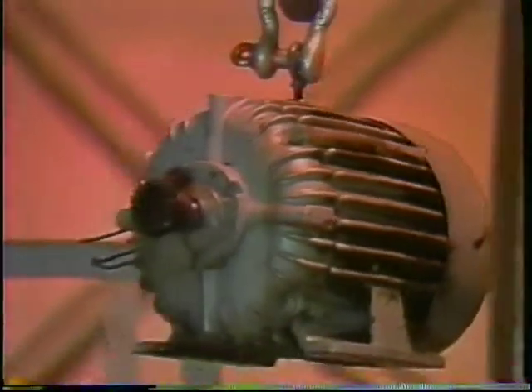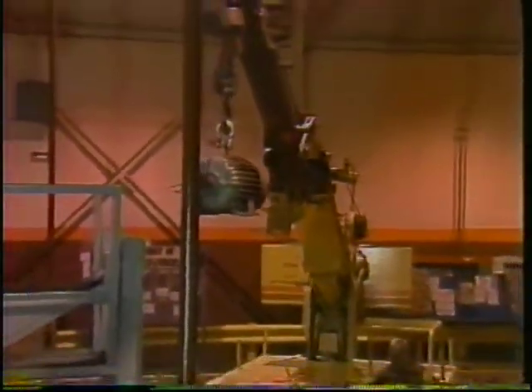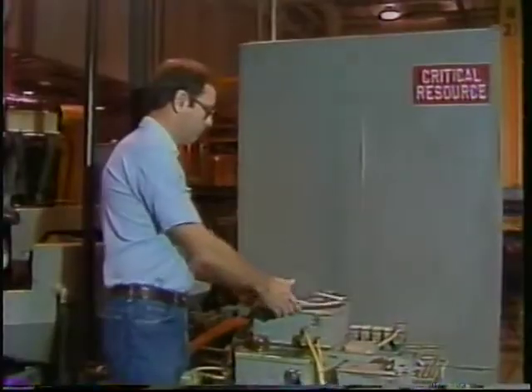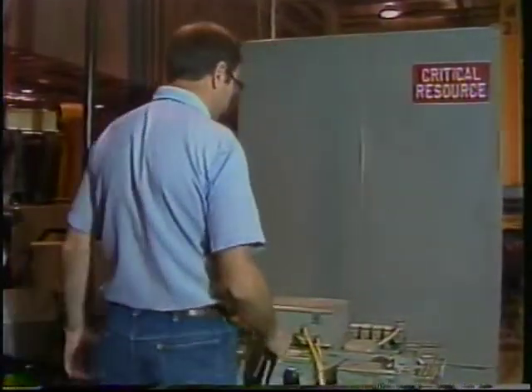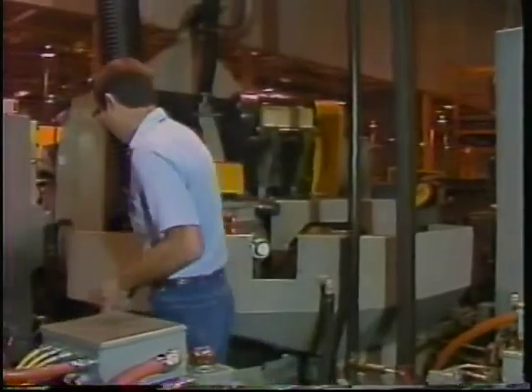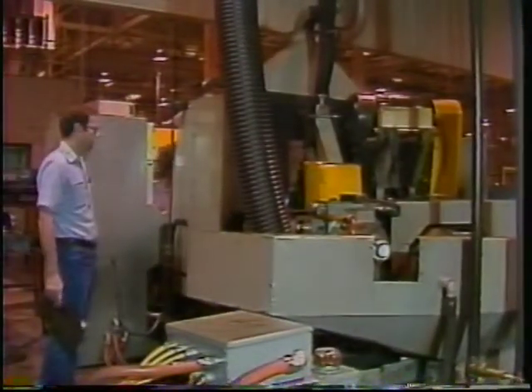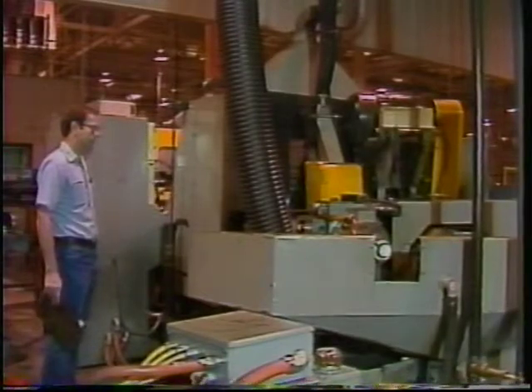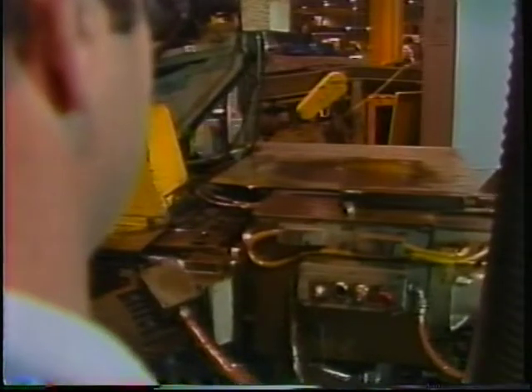Was the old motor especially dirty, or was it working in an especially hot environment? Talk to the operator or pull the work records on the motor to see if it has a history of tripping its overloads or breaking down some other way. You might also make sure the operator understands the limitations of the motor and has not been overloading it in some way or starting and reversing it too often.